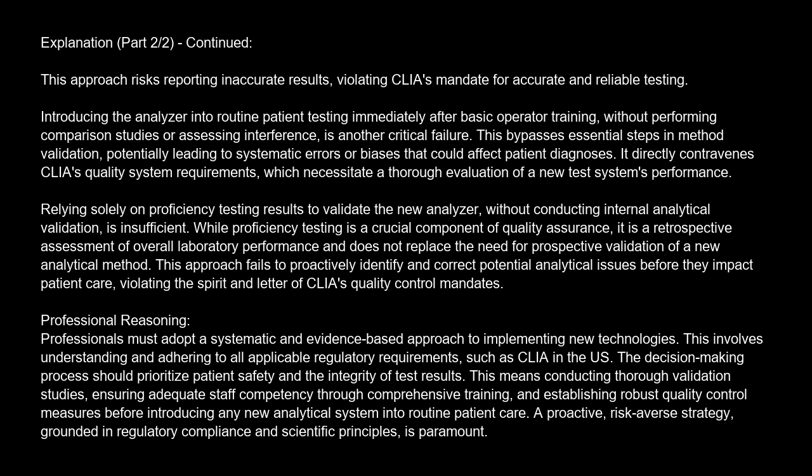Professional reasoning. Professionals must adopt a systematic and evidence-based approach to implementing new technologies. This involves understanding and adhering to all applicable regulatory requirements, such as CLIA in the U.S. The decision-making process should prioritize patient safety and the integrity of test results. This means conducting thorough validation studies, ensuring adequate staff competency through comprehensive training, and establishing robust quality control measures before introducing any new analytical system into routine patient care. A proactive, risk-averse strategy, grounded in regulatory compliance and scientific principles, is paramount.